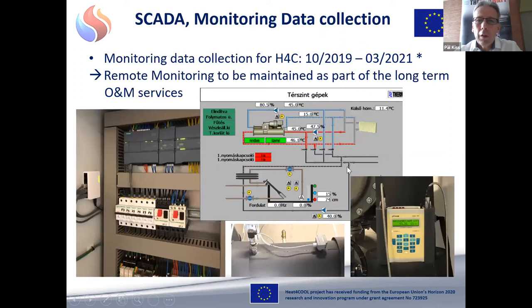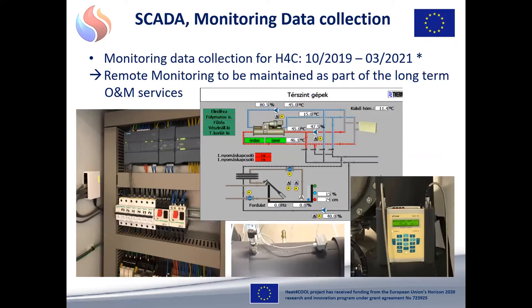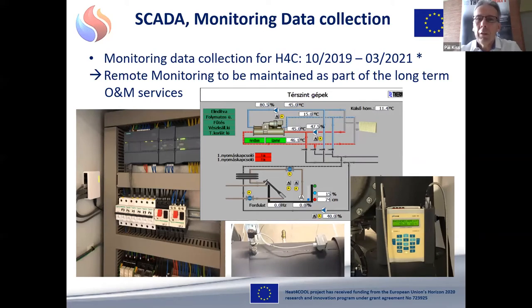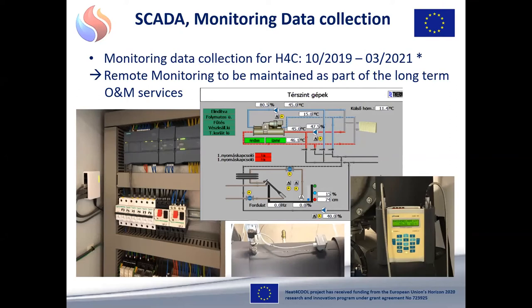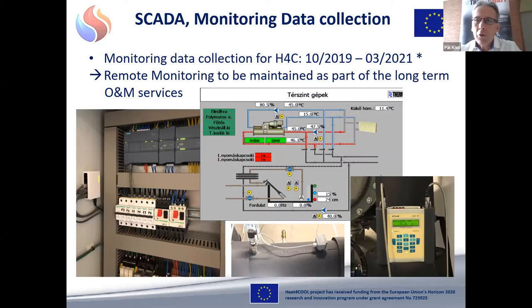So of course, for this, we installed our own SCADA system. And an important part of that installation was to monitor our results. We were the first site where we started the monitoring, in 2019, in October. And since then we have monitored the system. Basically, we monitored the flows, temperatures, pressures, so the efficiency of the heat exchange. The results will be explained by Rossano very soon from our side. We can say that we achieved good development in the efficiency of the whole system in the heat exchange, and it was all proven that such a system can work at large scale.